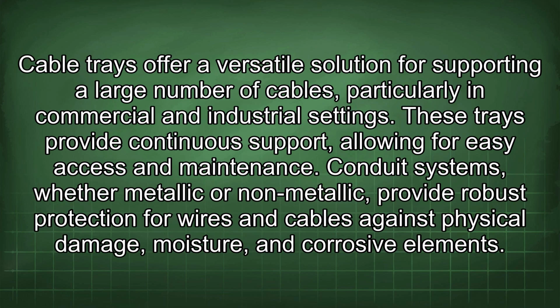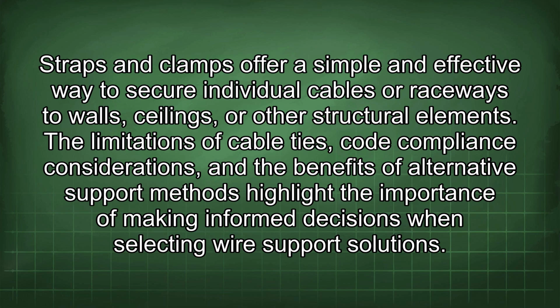Cable trays offer a versatile solution for supporting a large number of cables, particularly in commercial and industrial settings. These trays provide continuous support, allowing for easy access and maintenance. Conduit systems, whether metallic or non-metallic, provide robust protection for wires and cables against physical damage, moisture, and corrosive elements. Straps and clamps offer a simple and effective way to secure individual cables or raceways to walls, ceilings, or other structural elements. The limitations of cable ties, code compliance considerations, and the benefits of alternative support methods highlight the importance of making informed decisions when selecting wire support solutions.